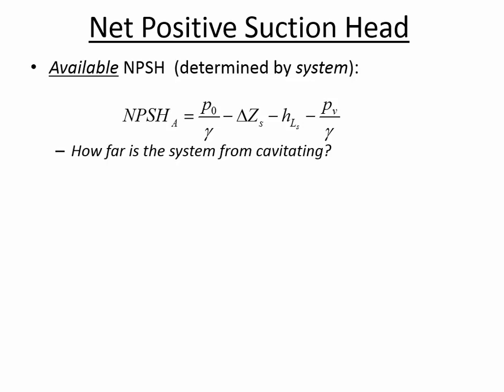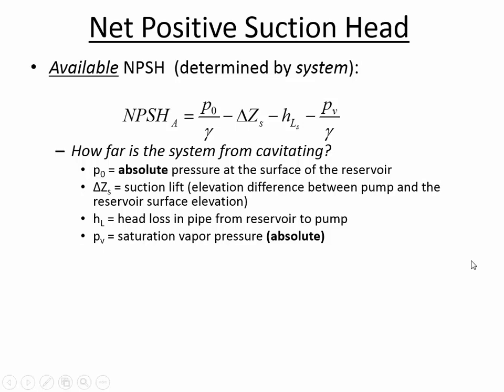But it's not just suction. It is the head loss due to pipe friction and also the local losses, and then also the vapor pressure itself. And the warmer the water, the greater the risk is that it'll cavitate, because warm water has a higher vapor pressure. Vapor pressure is a function of temperature of the liquid. So warm water that's being lifted a high amount is at risk of cavitation.